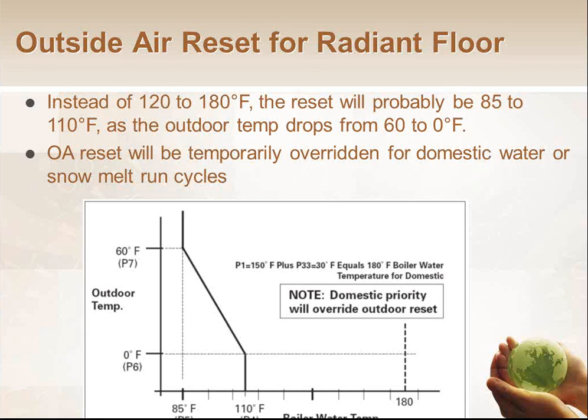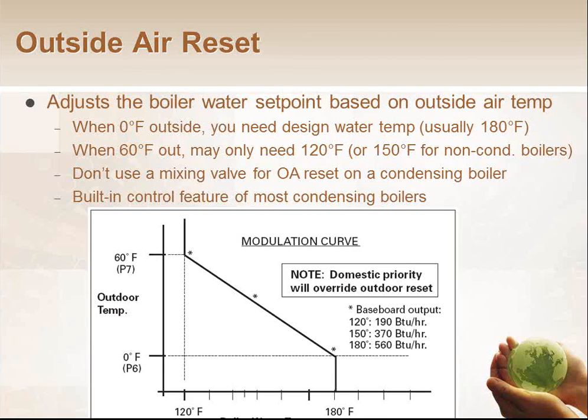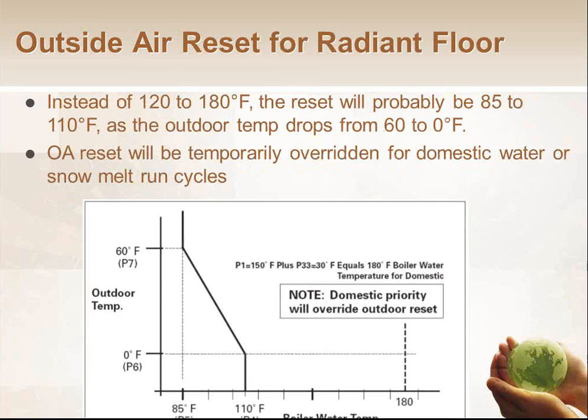If you do have a radiant floor system where you're operating with much cooler water temperatures, you can still do outside air reset. It just won't be as dramatic of a reset, right? So instead of 180 degrees on a 0 degree day, you can give me 110 degree supply water on a 0 degree day, right? And as it gets warmer outside, up to 60 degrees in this example, you can give me 85 degree water. So instead of resetting from 120 to 180, I'll reset from 85 to 110. By the way, even at 110 supply, I've got 95 degree return. I'm in a condensing mode. So with the radiant floor, I'm in a condensing mode all the time, right?